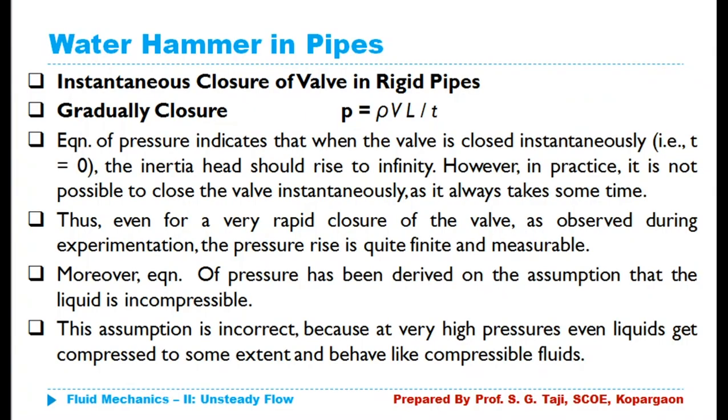So as we have discussed in the previous lecture, water hammer is the phenomenon of rising or decreasing the pressure in the pipes. Whenever we close the flow of liquid, or reduce the velocity of the flowing fluid to zero, the kinetic energy available in the water is converted into pressure energy and there will be a sudden pressure rise. Due to that sudden pressure rise, a pressure wave forms at the valve and moves in the upstream direction. While moving with that higher intensity of pressure, it hammers on the wall of the pipe, and that's why it is known as water hammer.